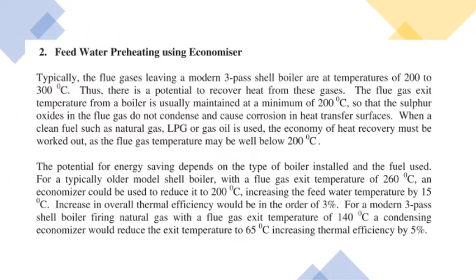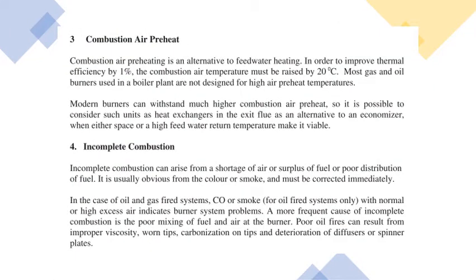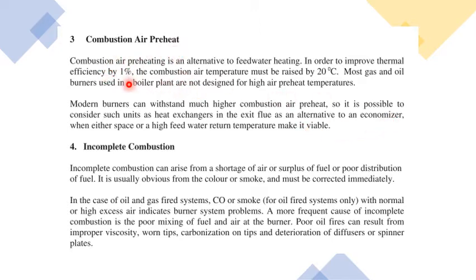The third point is combustion air preheating. Similar to the economizer, you can also install an air preheater to use the extra flue gas waste heat to preheat the combustion air. As a thermal rule, if the air temperature is raised by 20°C, boiler efficiency increases by 1%. Installing an air preheater is therefore another effective way to improve boiler efficiency.